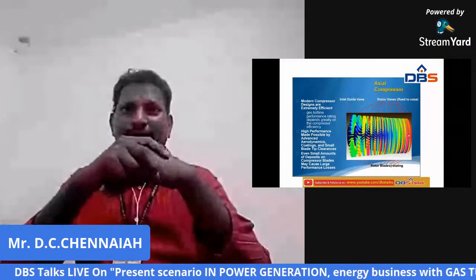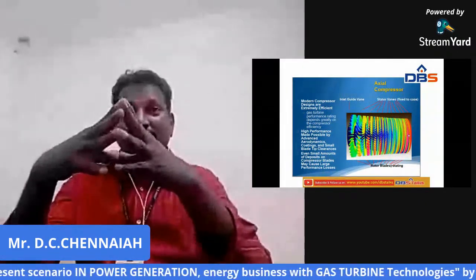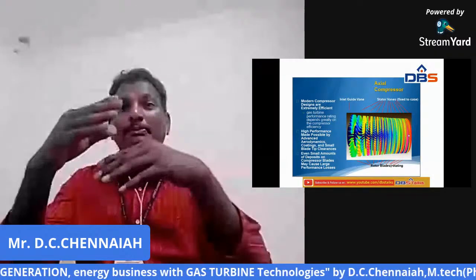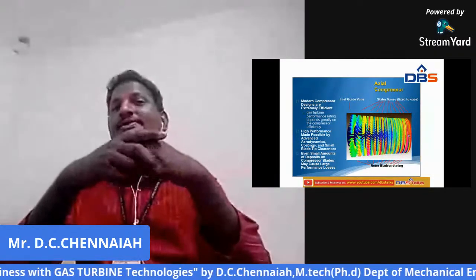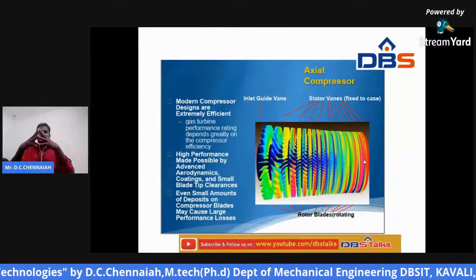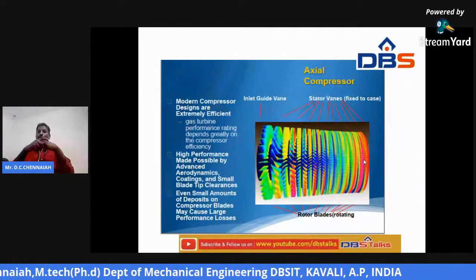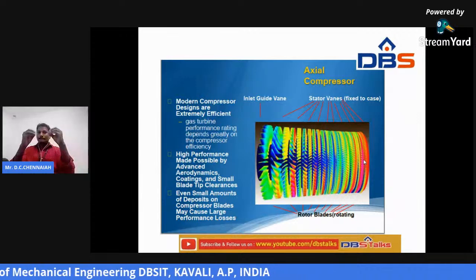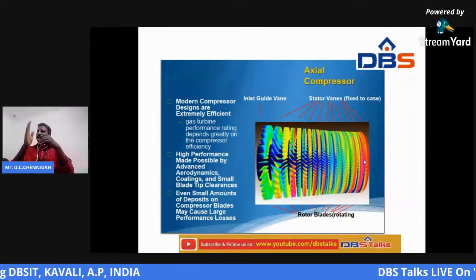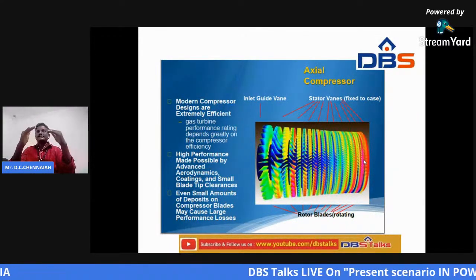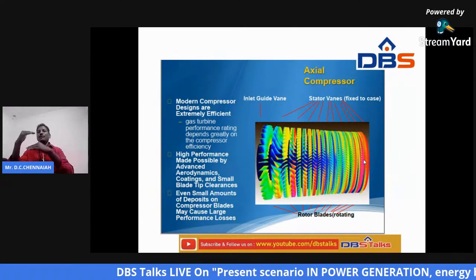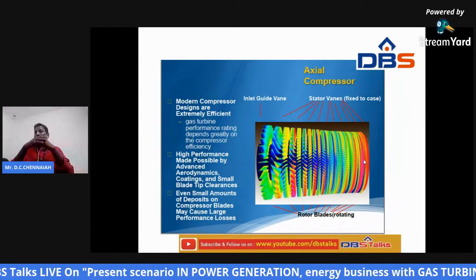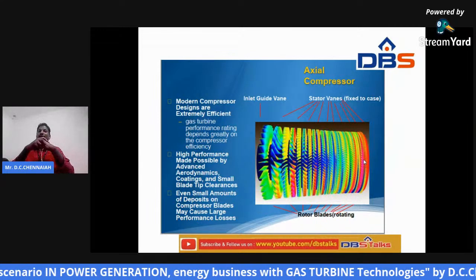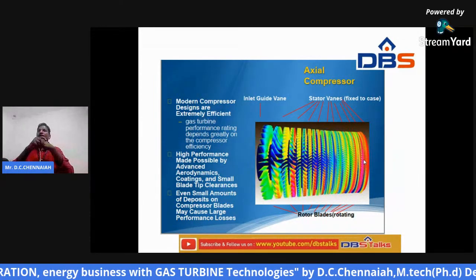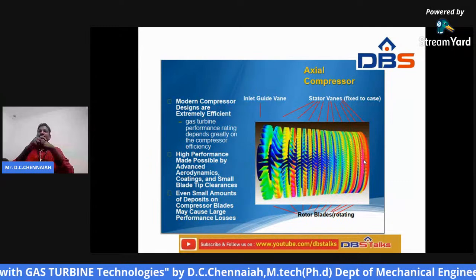Third point: even small amounts of deposits on the compressor blades may cause large performance losses. Performance losses mean work output losses, because deposits cause obstruction to the smooth flow of air over the compressor blades, which increases the work input. That is why it reduces the overall performance of the generating unit.